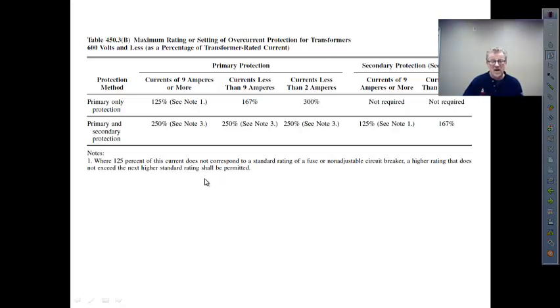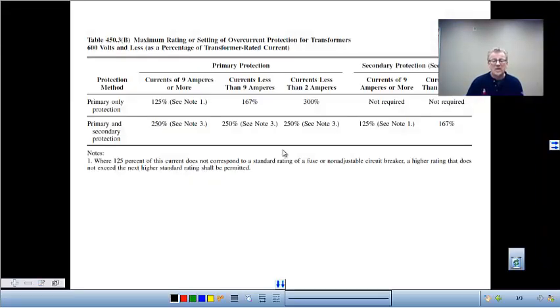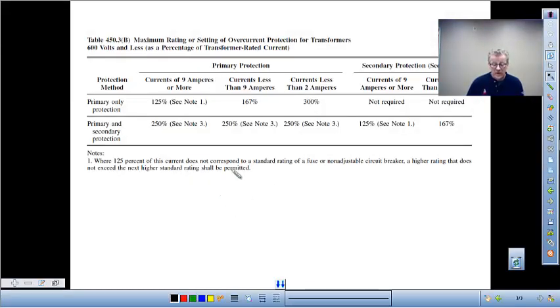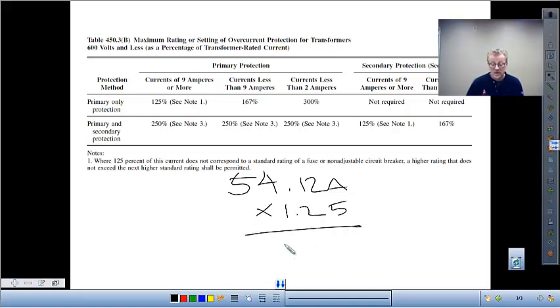So, what was our example? It was 45 kVA, and we had 54.12 amps from our calculation of full load current. Multiply that by 1.25, and we will end up somewhere in the neighborhood of 67.65 amps. Note 1, where 125% does not correspond to a standard rating, we're allowed to go to a higher rating that does not exceed the next higher standard rating.